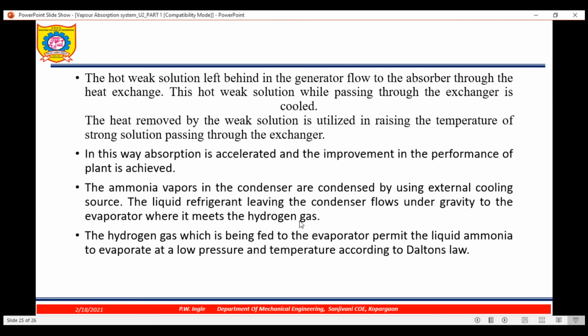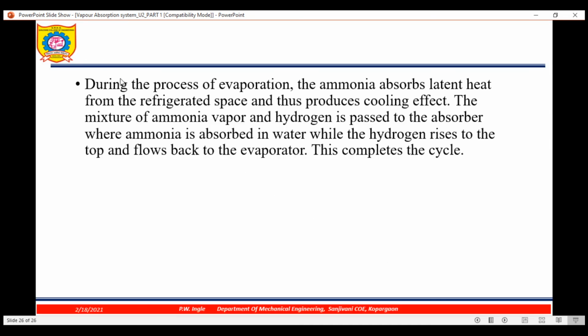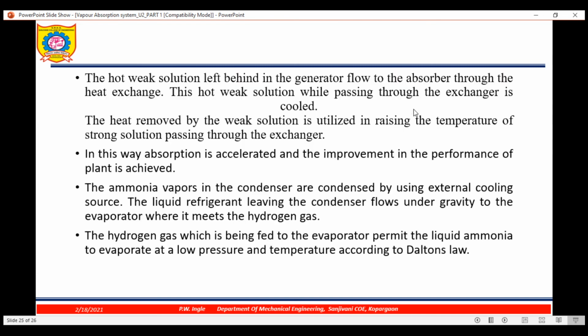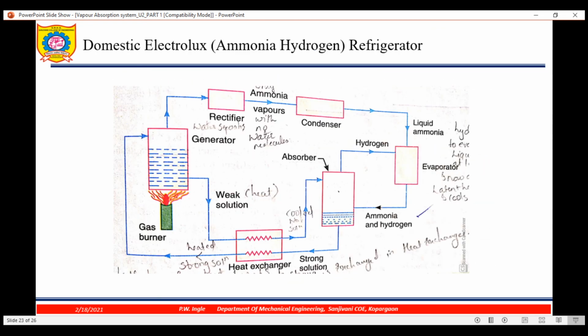where it meets the hydrogen gas. The hydrogen gas which is fed to the evaporator permits the liquid ammonia to evaporate at a low pressure and temperature according to Dalton's law. During the process of evaporation, ammonia absorbs latent heat from the refrigerated space and produces a cooling effect. So here we are getting the refrigerating effect.